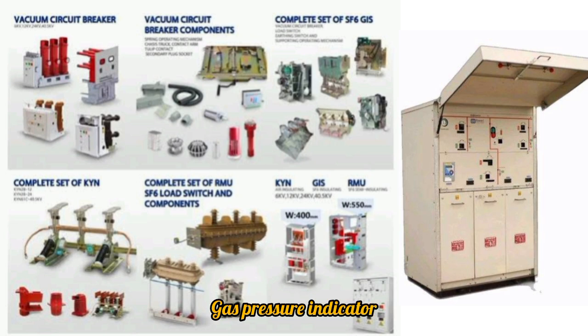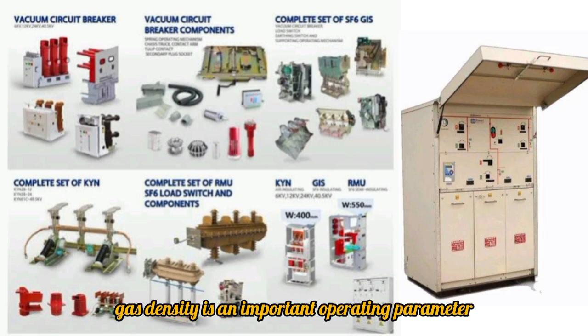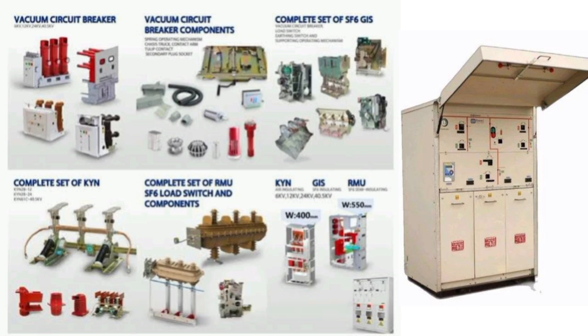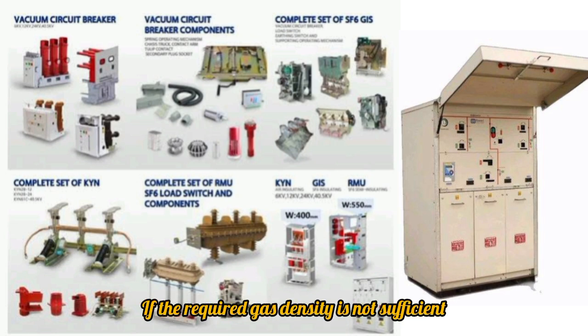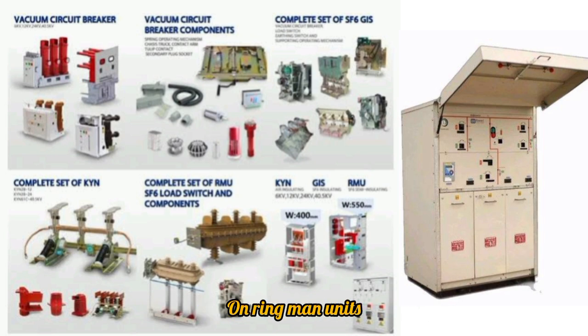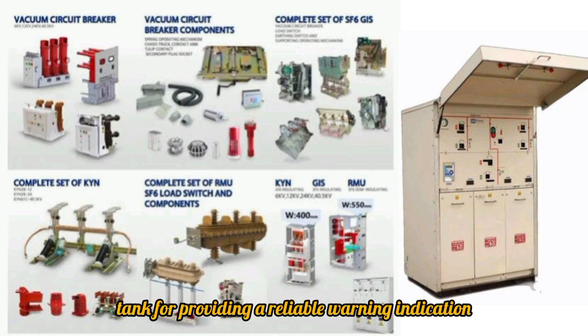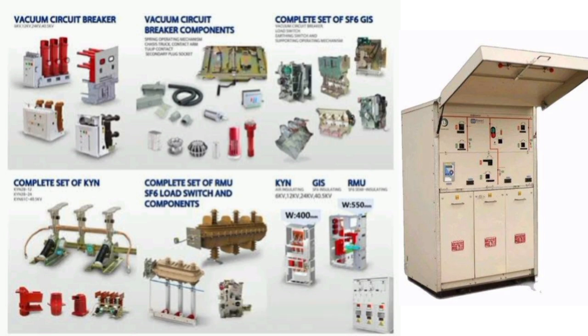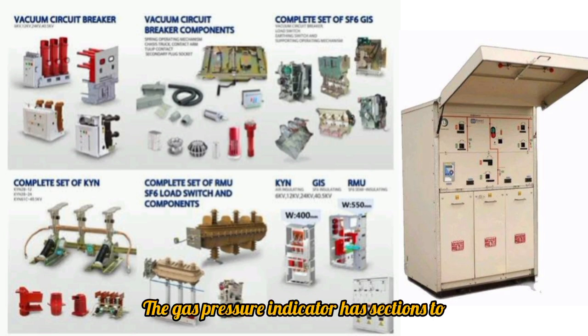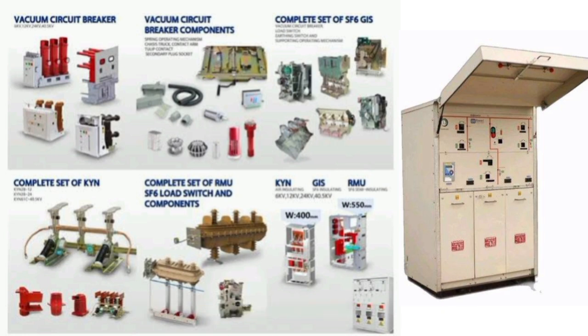Gas pressure indicator. Gas density is an important operating parameter for SF6 insulated MV equipment. If the required gas density is not sufficient, safe operation cannot be guaranteed. On ring main units, a gas pressure indicator is fitted to the tank for providing a reliable warning indication against low gas levels. The gas pressure indicator has sections to show the minimum pressure for safe operation.